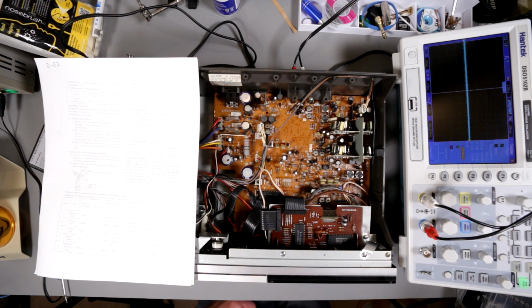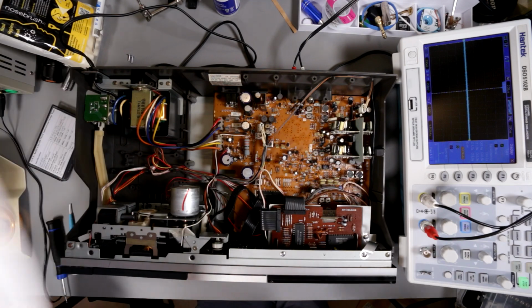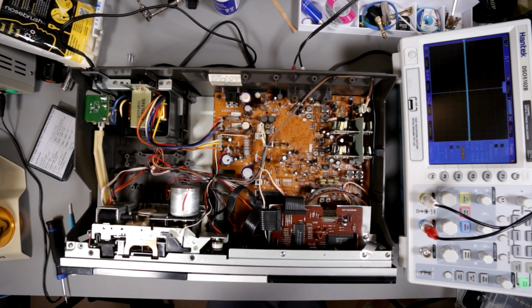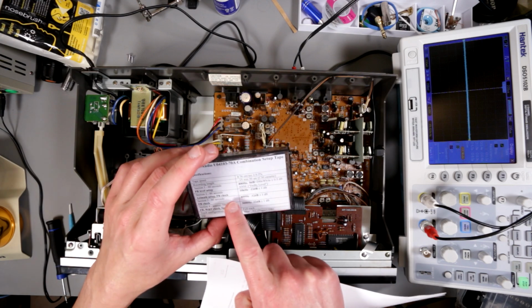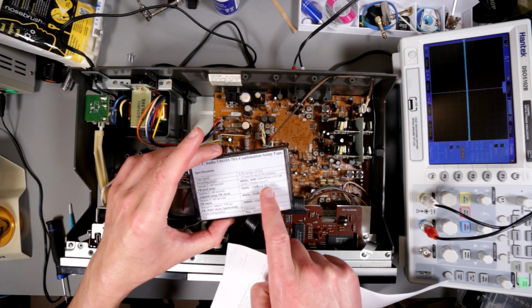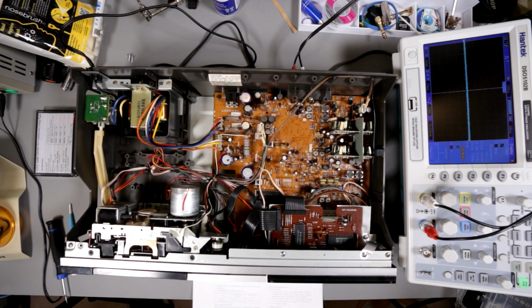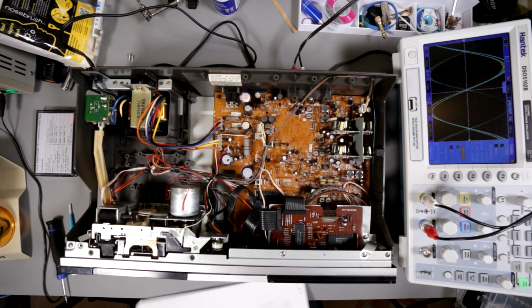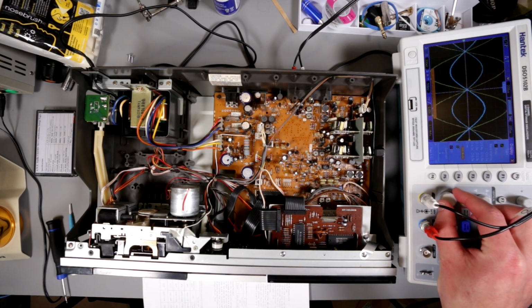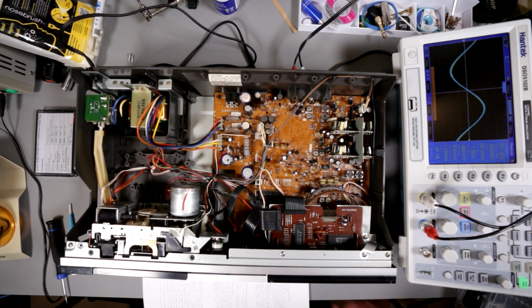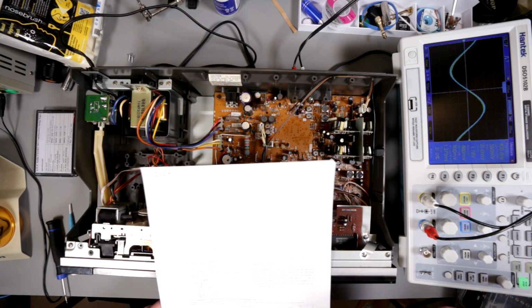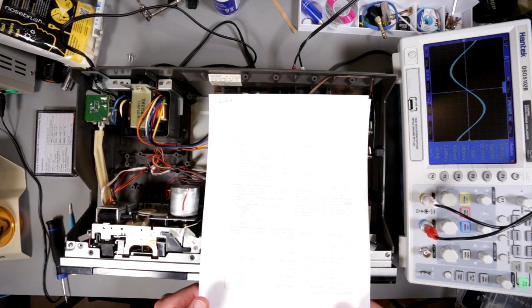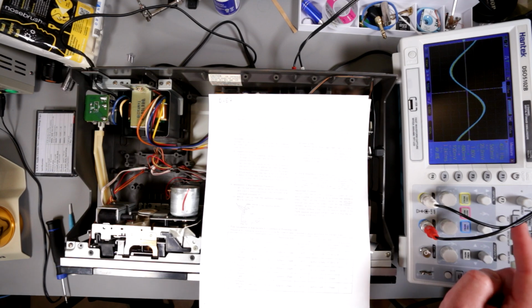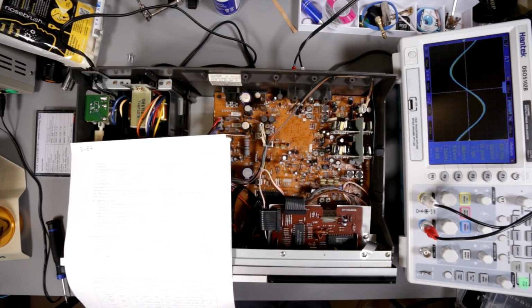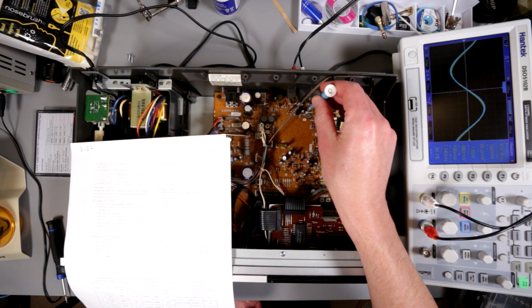Regular means not XY, but YT mode, where X is the time base. Okay, let's just play back, because from the very beginning, this cassette tape has 400 Hz, 0 dB at essentially NR Dolby level. And let's see. So this is our level. Let's do measure. We have 400 Hz, 516 millivolts RMS on one channel and 520 on the other. So we have to reduce it slightly. Okay, use a ceramic screwdriver and just start reducing.